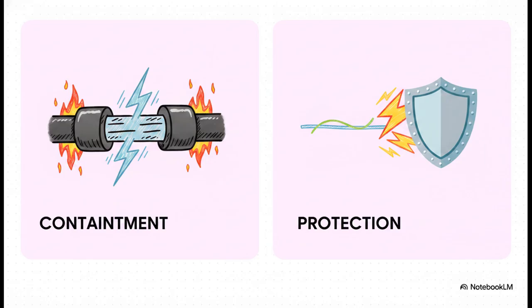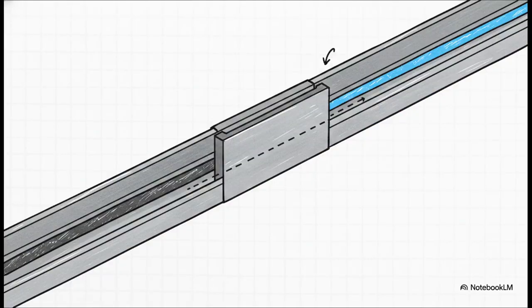So our goal isn't to protect the environment from the cable, it's to protect the safe low-energy IS circuit from the intrusion of outside energy. If a massive power cable shorts and dumps energy into our delicate IS cable, our safe circuit instantly turns into a lethal ignition source. Because of that exact risk of energy intrusion, intrinsically safe cable rules are absolutely uncompromising.